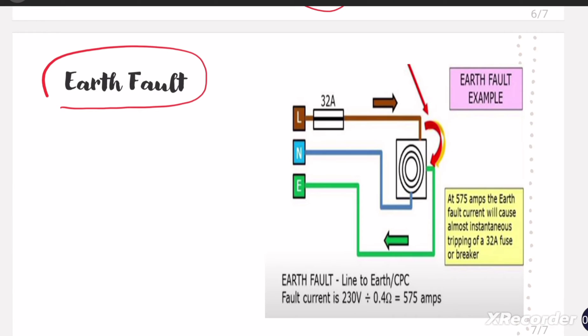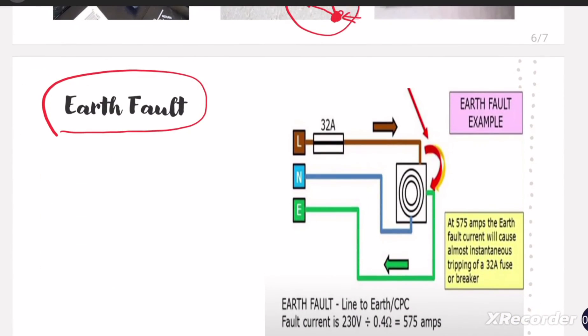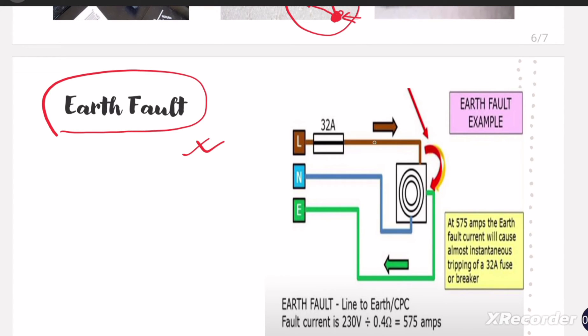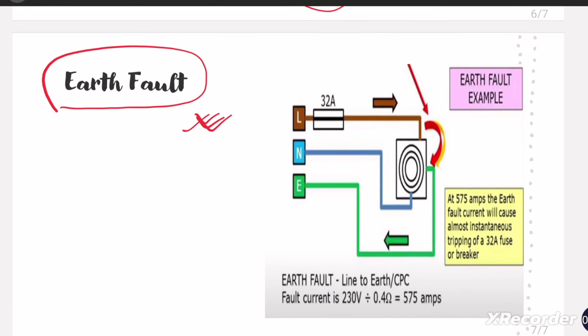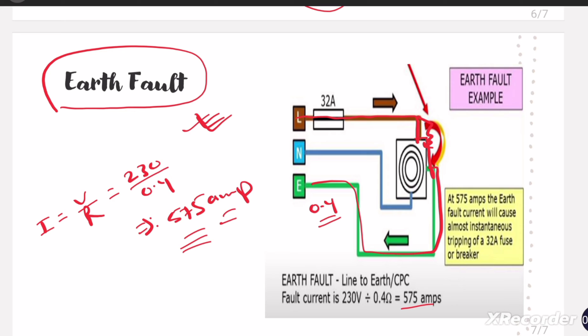Now let us understand earth fault. In short circuit, the line and neutral get shorted with negligible resistance. Similarly, in earth fault, the line and earth get short circuited with negligible resistance. For example, if the line touches the equipment body, the body attains high potential and current flows from the line through the cooker body to the earth wire. If the resistance of this path is 0.4 ohm, then I = 230 / 0.4 = 575 amperes. That condition is called earth fault.